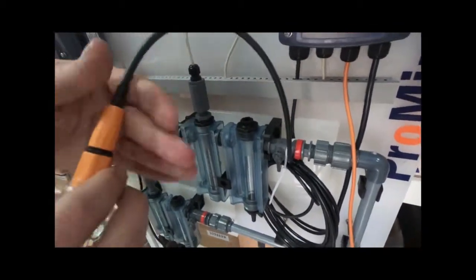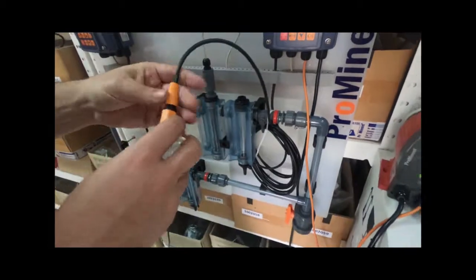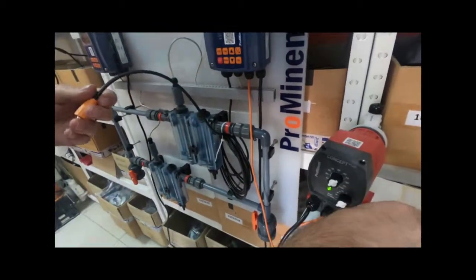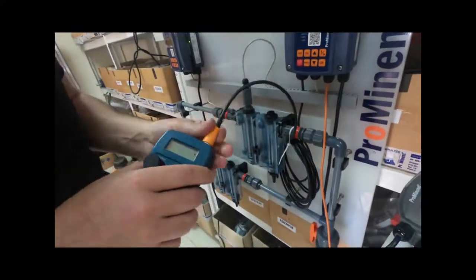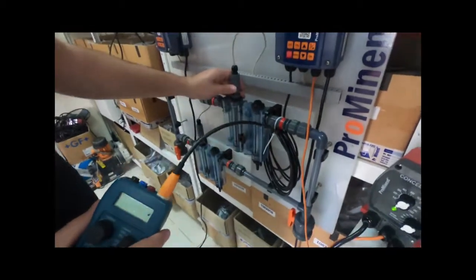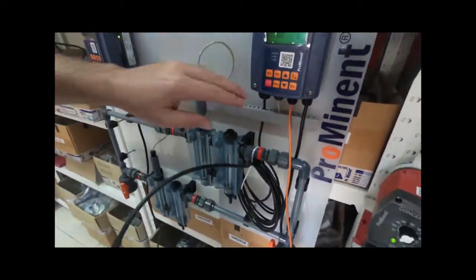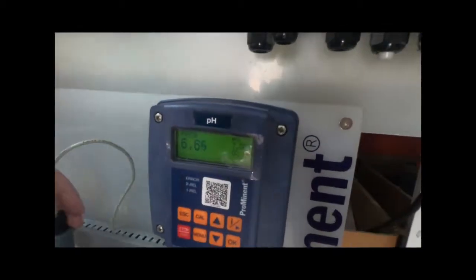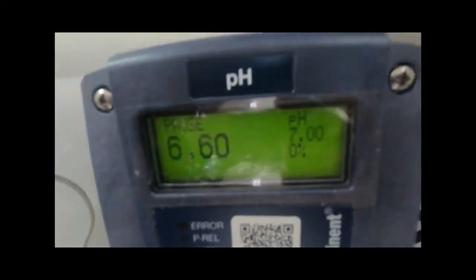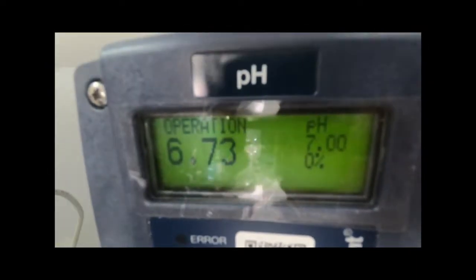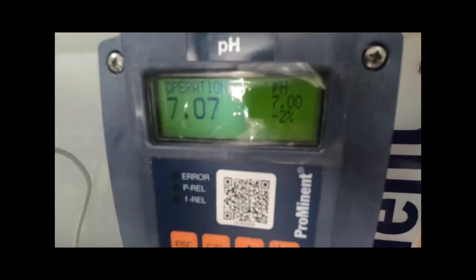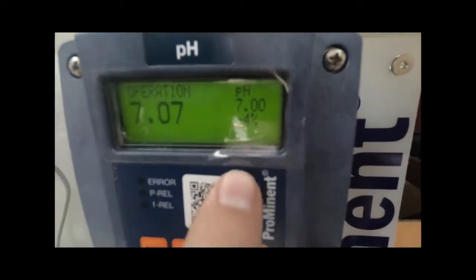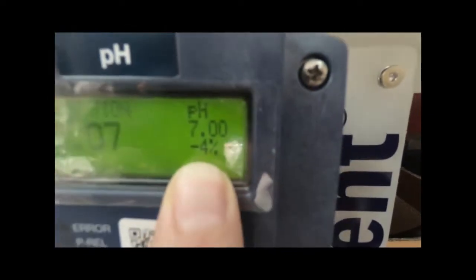So for this system we are going to use the simulator that is connected already with the pump. So now as the set point is 7, we have here 0, and we have here pause because the flow switch has no contact with water. What we are going to do is push it down until we have contact, and then we run the simulator. Now it's more than 7. If you can see here, we have -4%. That means it's a little bit above the set point. When we go below the set point, it will go to 0.